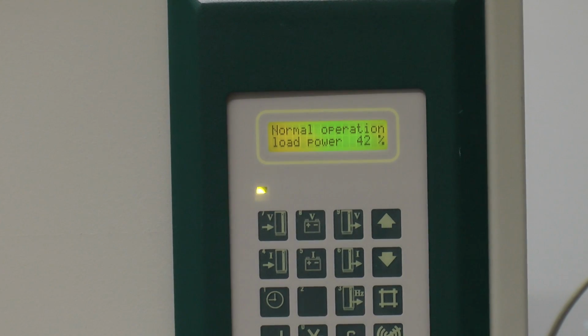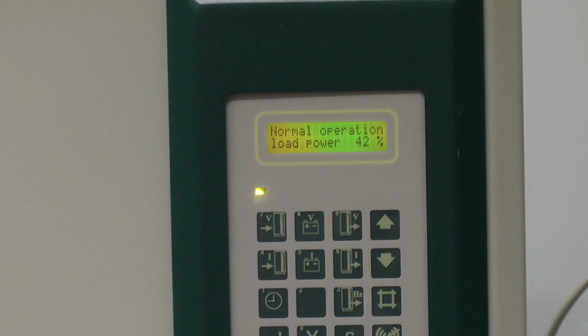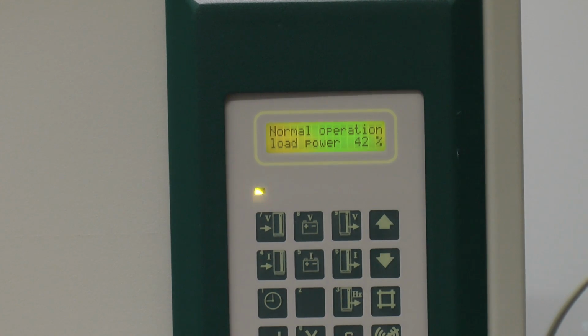Greetings. What we've got here is a rather large UPS, an APC Silcon DP320, and it's not a happy one. As you can see, it's starting to lose communication with itself. It's been sending countless emails out. Last night I received an email saying that it's actually turned itself off when it hadn't. So it's end of life. The batteries are 8 years old, so I'm going to put it into bypass, and at some point we'll shut it down and take it to bits.